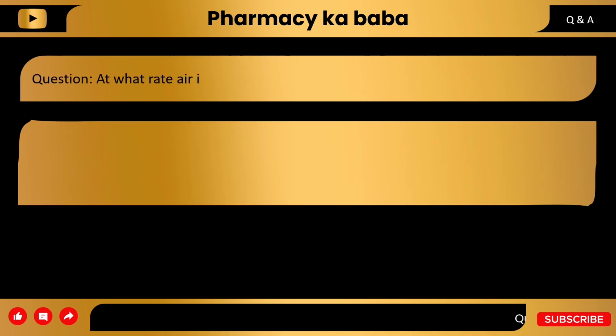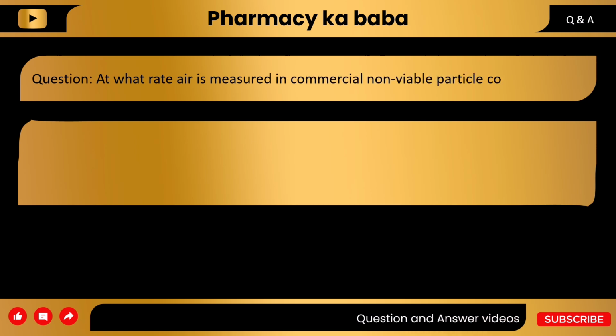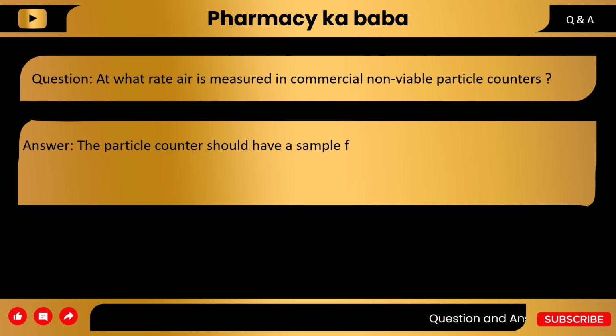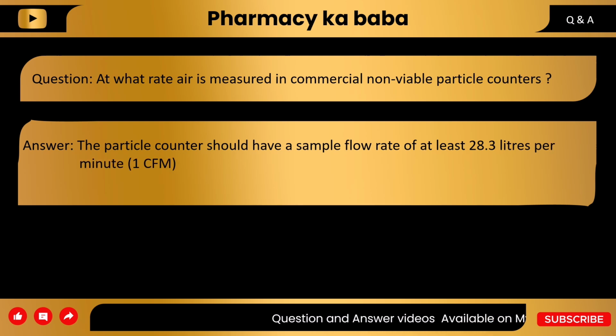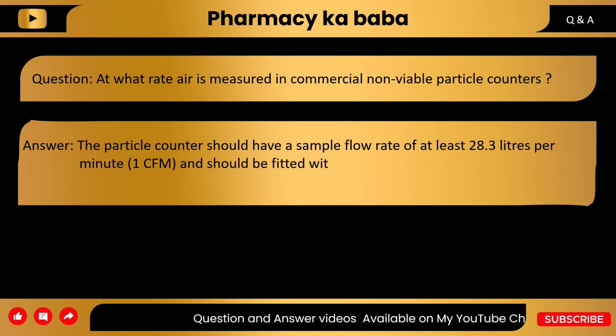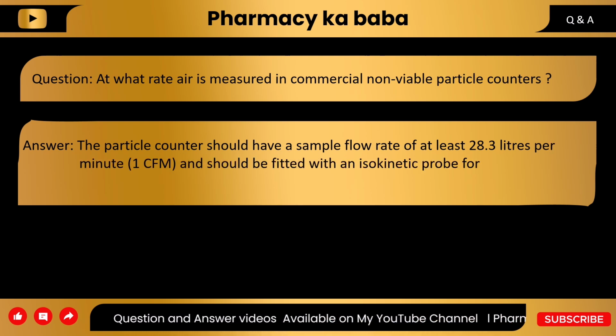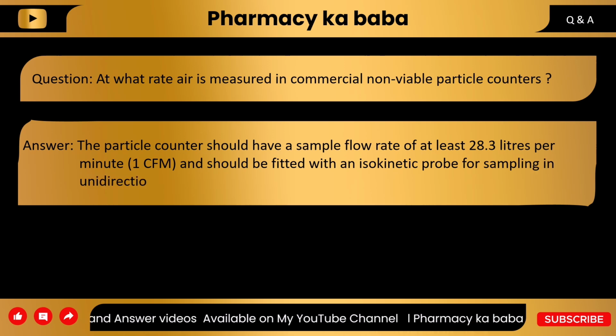Question. At which rate is air measured in commercial non-viable particle count? Answer. The particle counter should have a sample flow rate of at least 28.3 liters per minute. One CFM, and should be fitted with an isokinetic probe for sampling in the unidirectional flow zone.